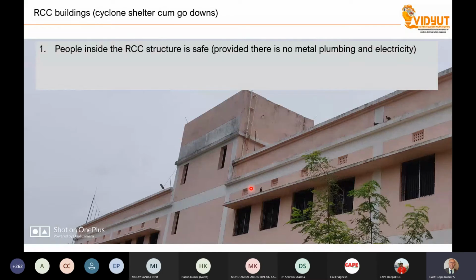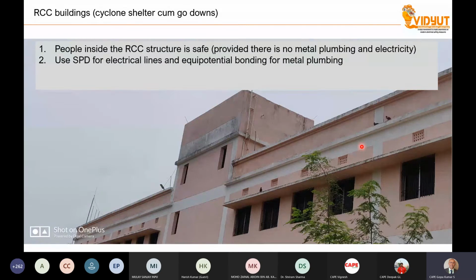Now, for cyclone shelters, this kind of RCC building, the people inside the building are protected, provided there is no metal plumbing and electricity inside the building. If there is metal plumbing and electricity inside the building, you have to make an equipotential bonding. Otherwise, people inside are protected. Now, whatever rod and down conductor you are going to give for these kinds of buildings is to protect the structure. Otherwise, lightning will strike the structure and the concrete or a piece of concrete may break.